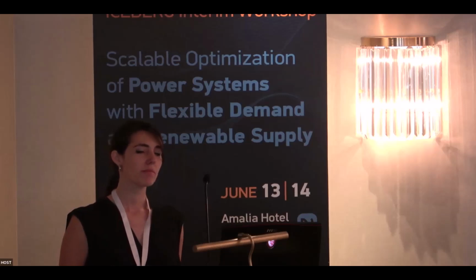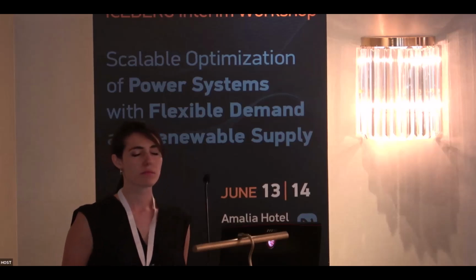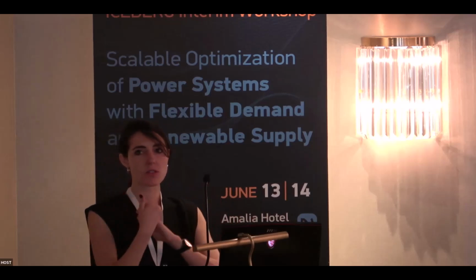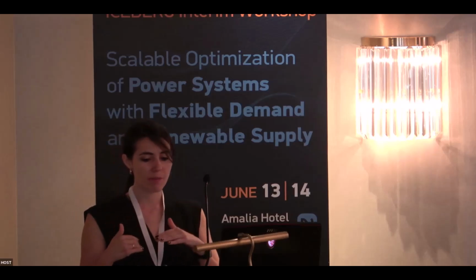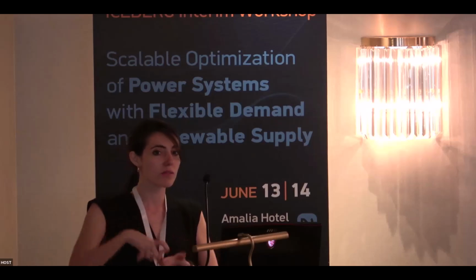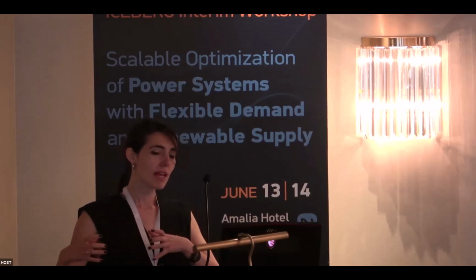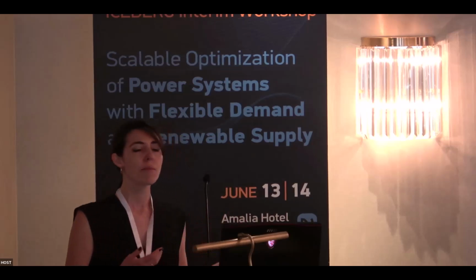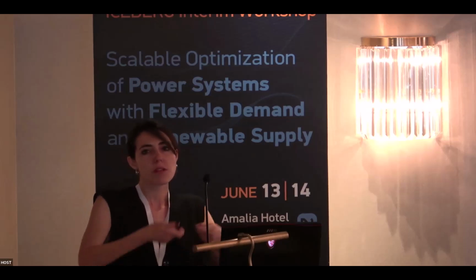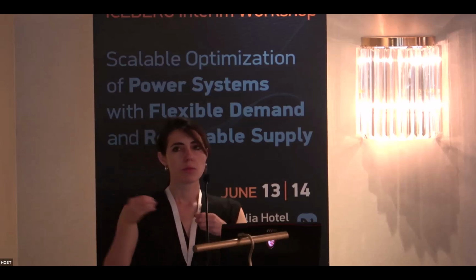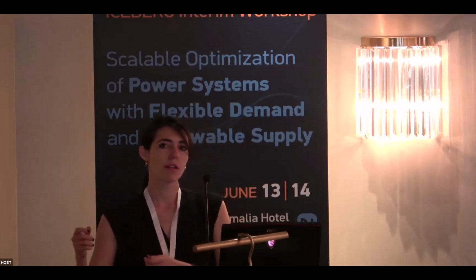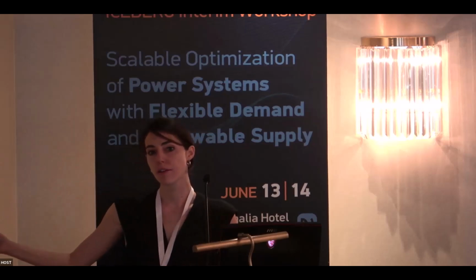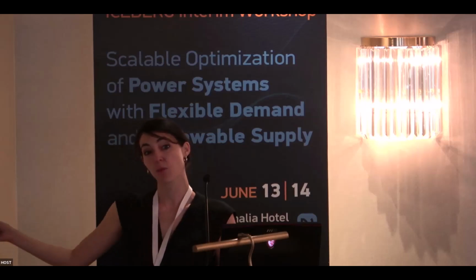No, it's a different approach. It is a different way of finding it, and it is possible to approach it this way because we have an EENS constraint and not a LOLE constraint. But I would say it is a different way to approach it. It gives you the information of what would be the penalization of load shedding that we would incur at a certain level of investments in order to meet a certain criterion on ENS, not LOLE, because that would be a different problem.